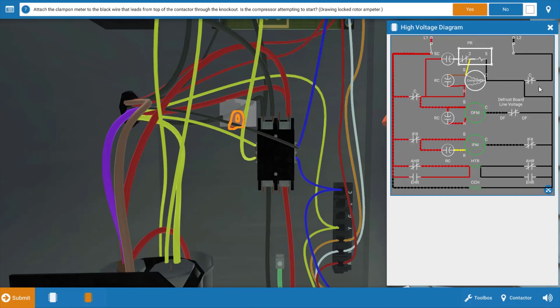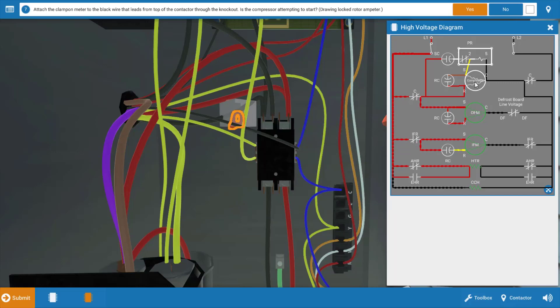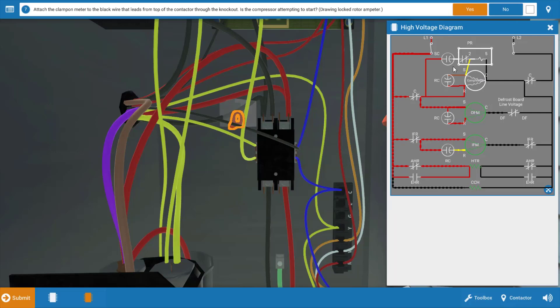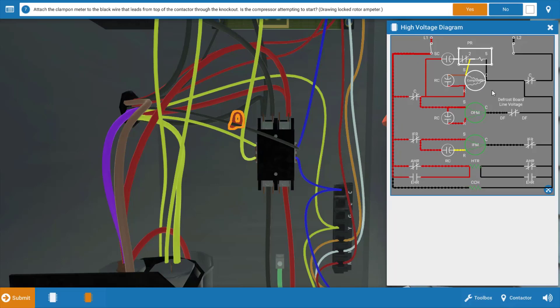Now, when we look at the wiring diagram, here's our compressor right here. What would cause this to try to start? Well, what this means is more than likely our run winding is engaged, but our start winding is not. So it's possible we have an open start winding. But if you take another look, we've also got those set of contacts that we talked about between terminals one and two are in series to that start winding. In addition, both the run and start capacitor are also in series to the start winding. So a malfunction in any of these starting components could cause the compressor to draw locked rotor amperage and cycle on its overload.